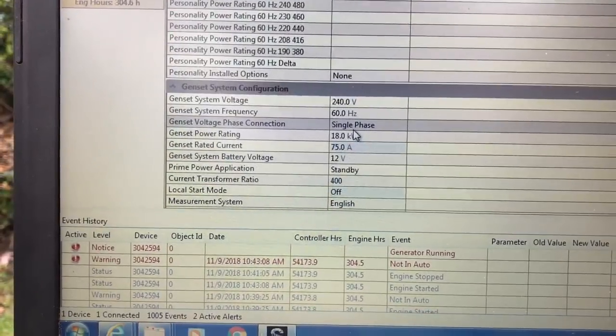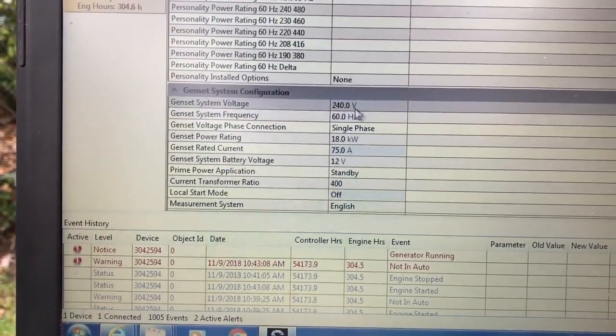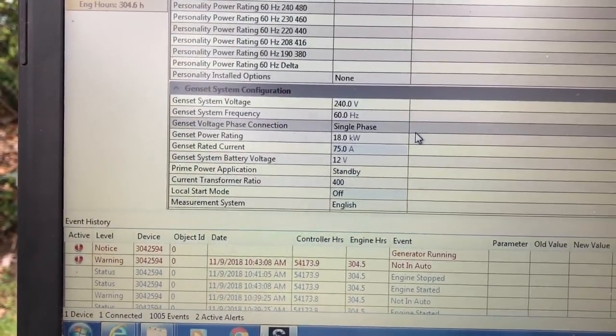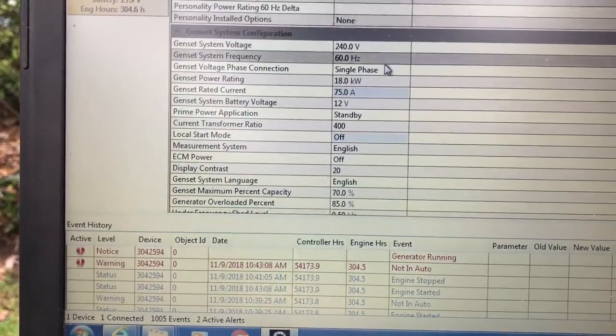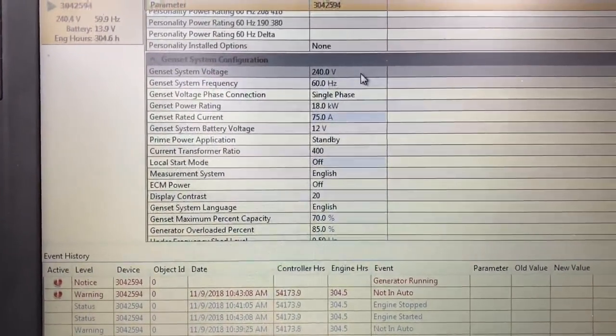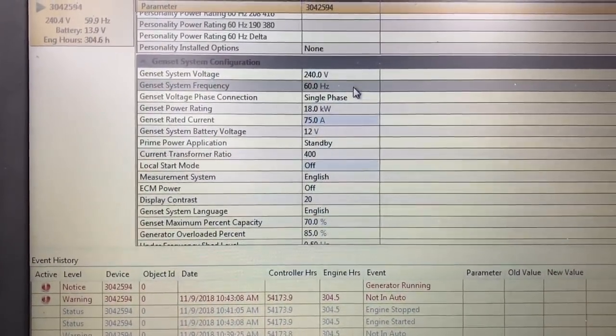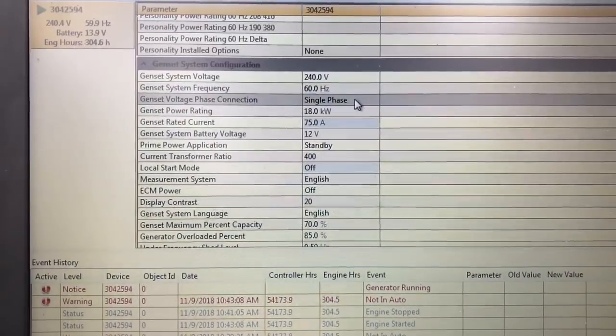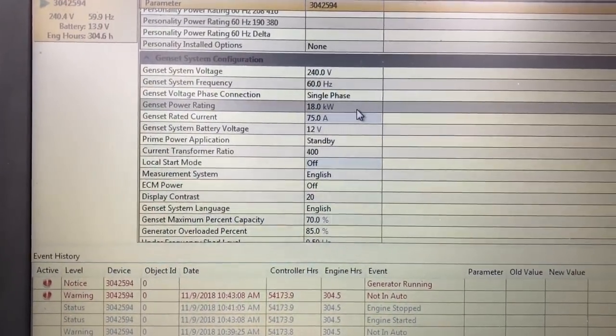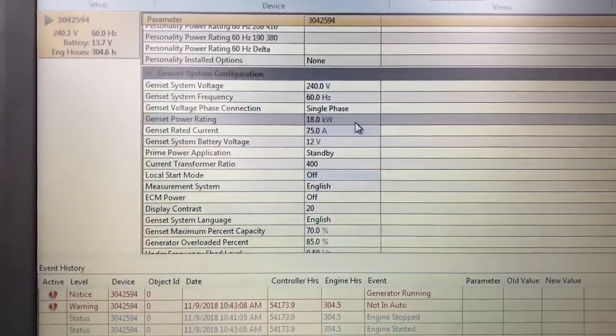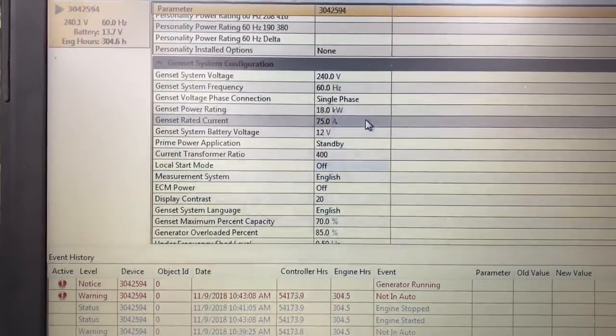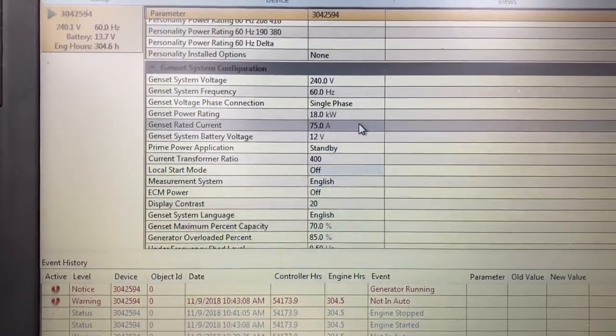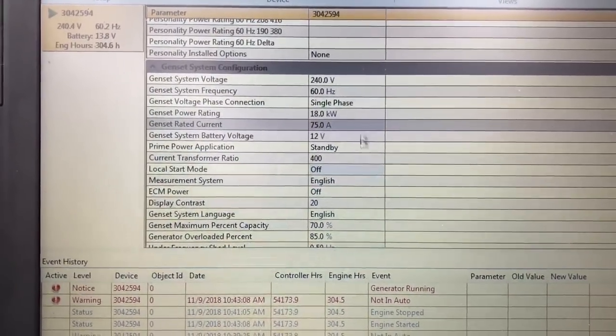What I should actually do is load it up and you'll see some of those things actually come to life. My configuration is for 240 volts at 60 hertz on the single phase unit. It's at 20kW, but seriously it's really only an 18kW running on natural gas. 75 amps is my genset rated current.